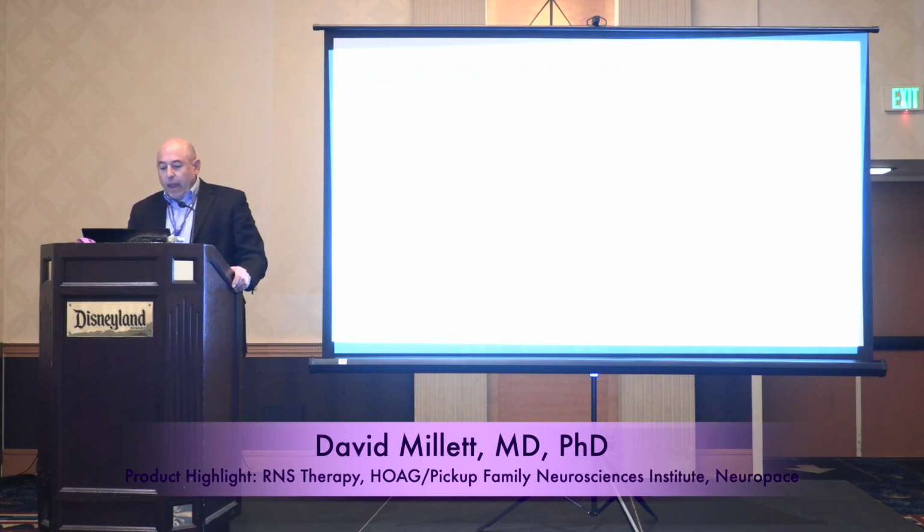And many of our patients are surprised that the RNS system is identifying over 1,000 or 2,000 seizure-like events per day. These are often called long episodes. They're not having 1,000 seizures per day, but oftentimes 1,000 times per day or more, there will be a brief electrical discharge that looks like the beginning of a seizure, and the RNS is trying to stop anything that might go on to become a seizure from doing so.